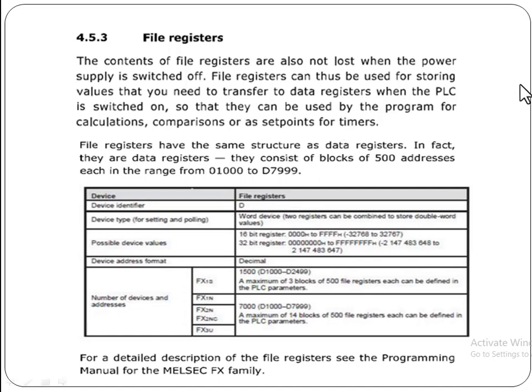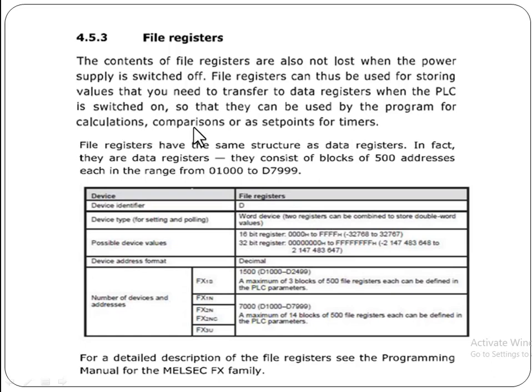File registers can thus be used for storing values that you need to transfer to data registers when the PLC is switched on. When the PLC is switched on, the values of the file registers are transferred to the data registers so that they can be used by the program for calculations, comparison, and as set points for timers.